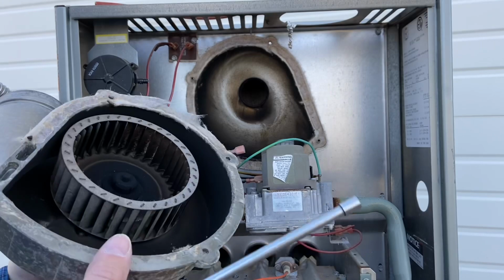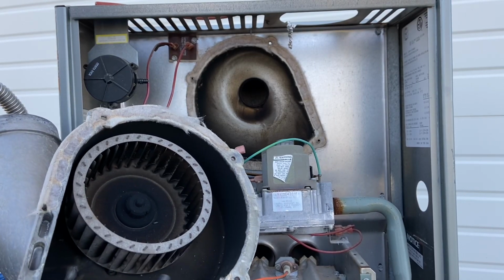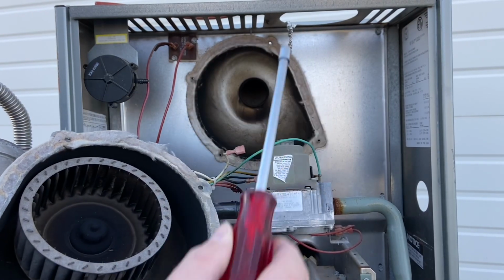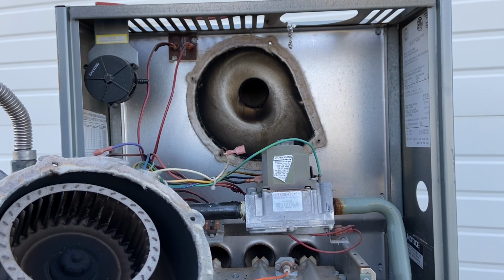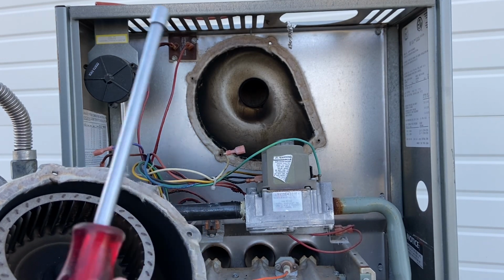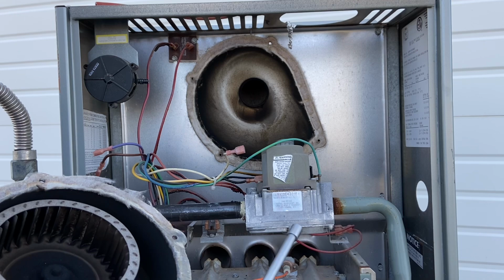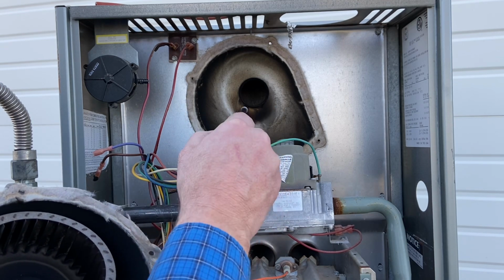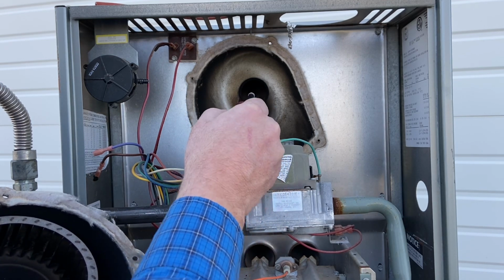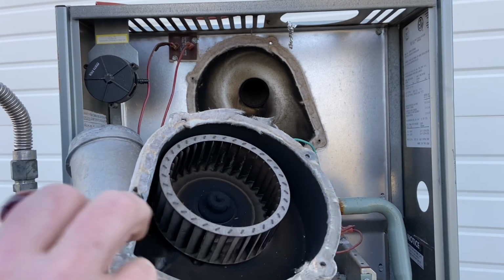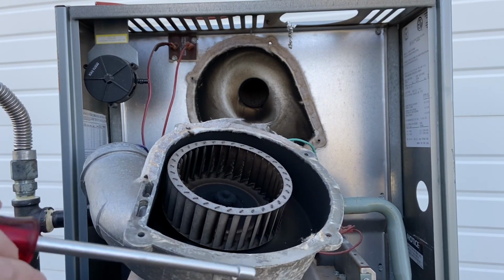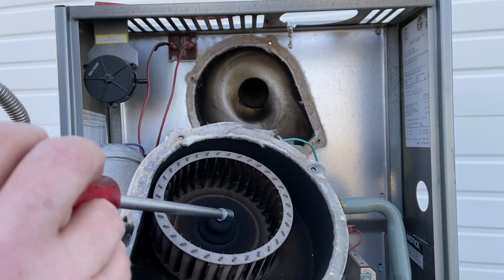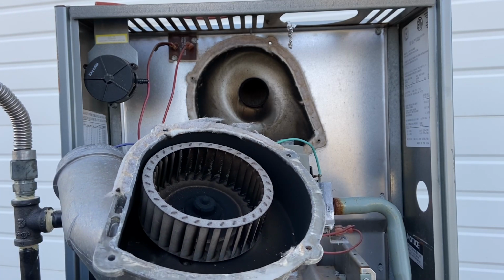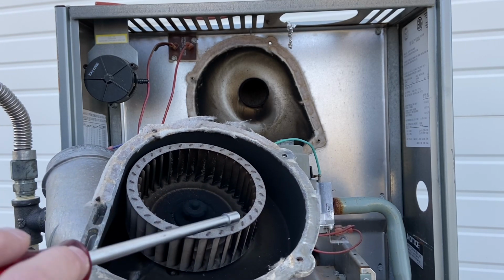If we pull this inducer fan motor out, you can see there's a lot of black on here and all around here. That's because this unit's running on propane right now and it's designed for natural gas. So it's a huge issue. You should never do that. We're breaking all the rules today. You can see all the soot built up in here. It's also building up inside the heat exchanger. And there's a ton of soot built up on this wheel right here and all through here. So this only ran for a few minutes with the wrong gas and it did this much damage.